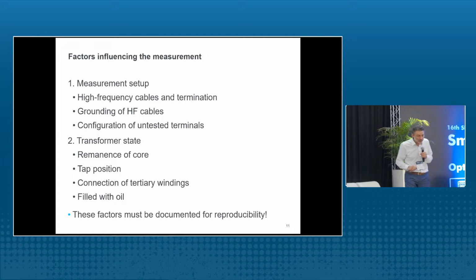But what is important is that FRA is used as a comparison. I need a fingerprint measurement when the winding is okay. Then I repeat the measurement later, and I compare both measurements to see if there is any shift of resonance frequencies. And if there's a shift, then I have a problem. If the curves are the same, everything is okay. But this means, of course, that you can reproduce your measurement very well.